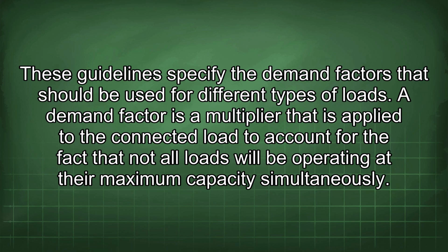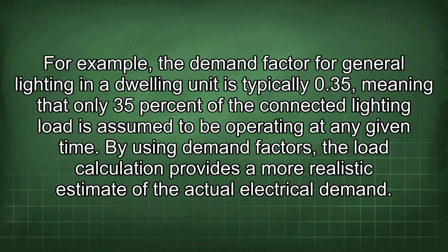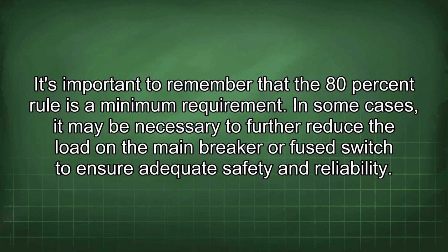A demand factor is a multiplier that is applied to the connected load to account for the fact that not all loads will be operating at their maximum capacity simultaneously. For example, the demand factor for general lighting in a dwelling unit is typically 0.35, meaning that only 35% of the connected lighting load is assumed to be operating at any given time. By using demand factors, the load calculation provides a more realistic estimate of the actual electrical demand. It's important to remember that the 80% rule is a minimum requirement. In some cases, it may be necessary to further reduce the load on the main breaker or fuse switch to ensure adequate safety and reliability.